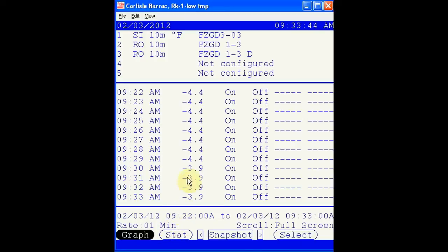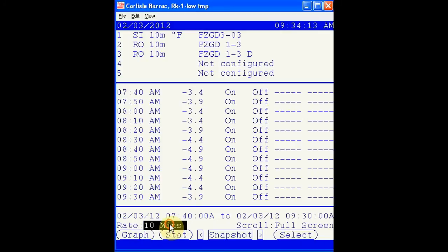For instance, note that at the top of the screen, these 3 points that are important to this evaporator are logged on 10-minute intervals. Because of that, if we view the graph at 1-minute rates, we're simply going to see duplicated information. Let's change this rate to 10 minutes to get better information and more information on the same screen.